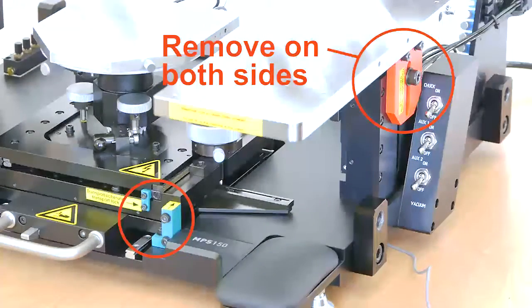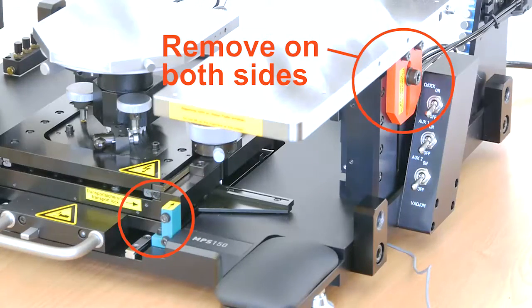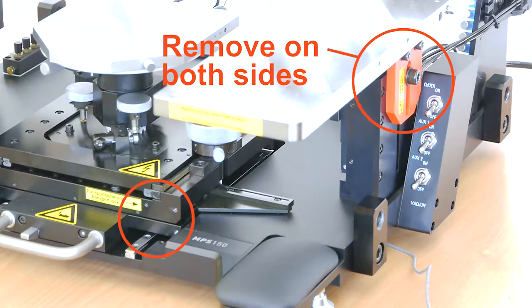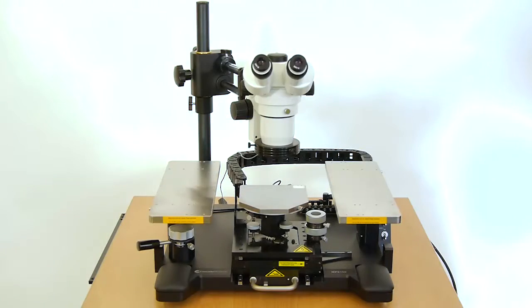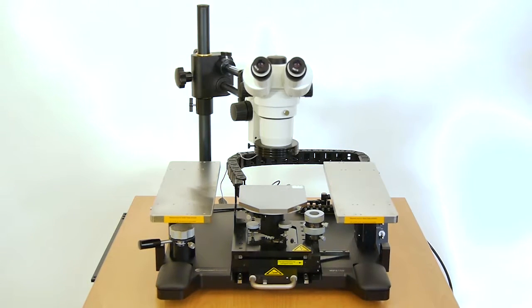After setup the probe station, remove the transport locks which secure the chuck stage and the plate movement. Now the MPS150 base station is ready for test. For setup the accessories, please see the quick reference guide.